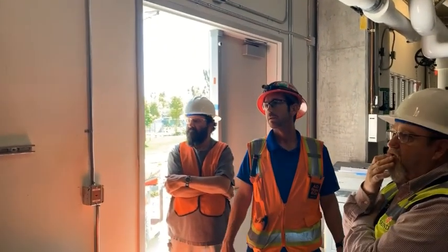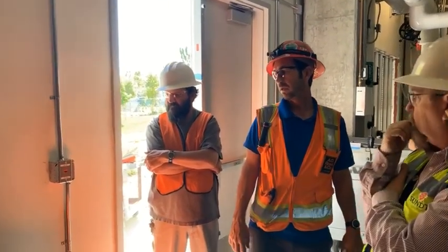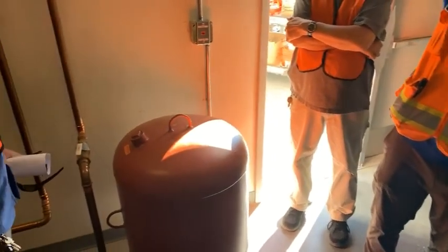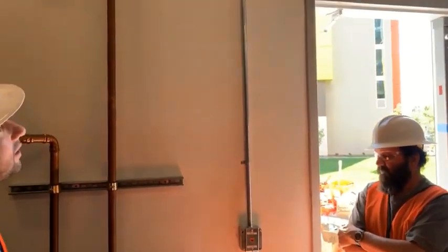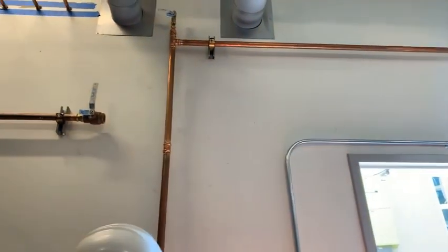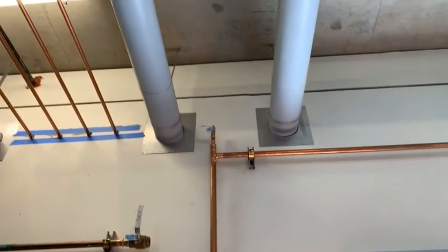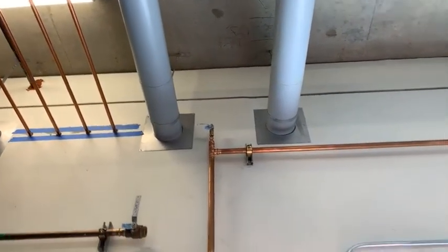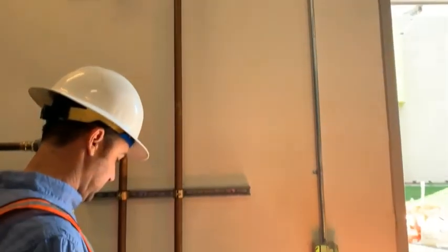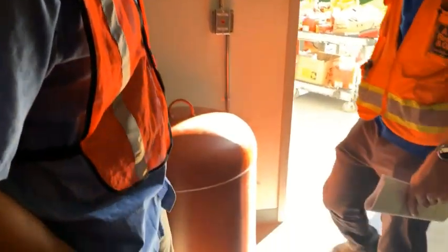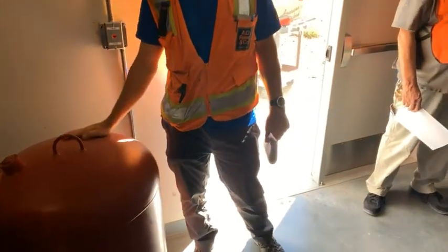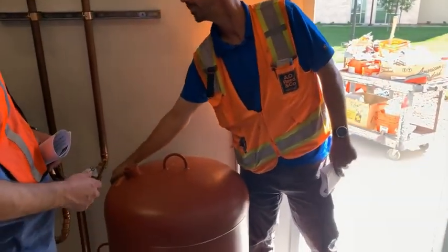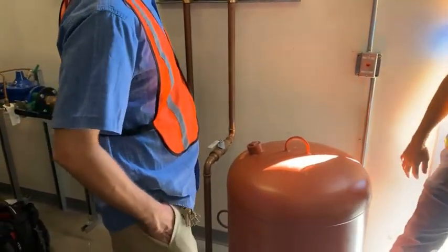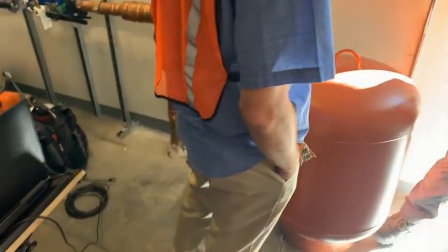Right, right. So where's the vent on this system now? Is there a vent? Right there. It's manual. Okay. So if you had to do any work on this line, you would just open that valve right there to vent, because you don't want air stuck in that pipe. Okay, there's the other store. And this is drain domestic. There is one on the union, I guess so. It is possible though. Anything's possible.